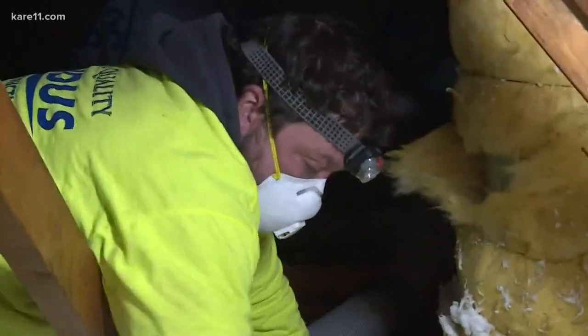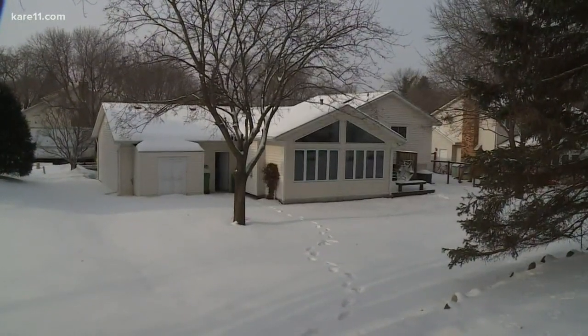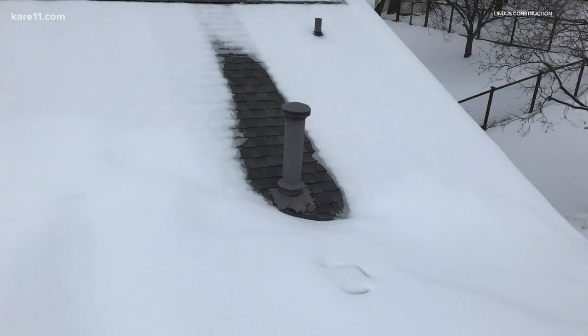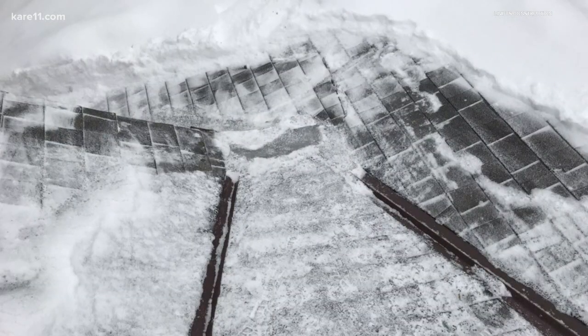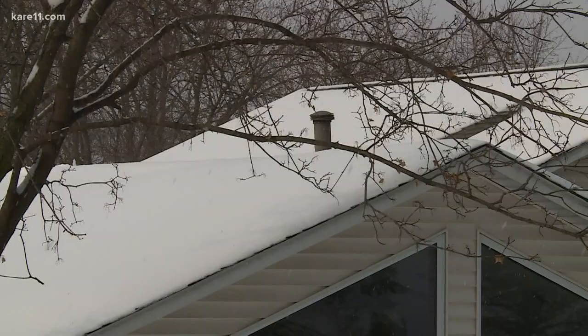This house had an addition put on it, and what they did is they framed over the top of the old part of the house, so they couldn't get the proper attic air chutes in there — that's the intake that comes into the attic. The ultimate goal in wintertime is to try to get your attic at the same temperature as it is outside. That gives you your best chance to not have an ice dam occur. If you don't have the proper intake, that warm air can just sit in your attic and really start to melt everything.